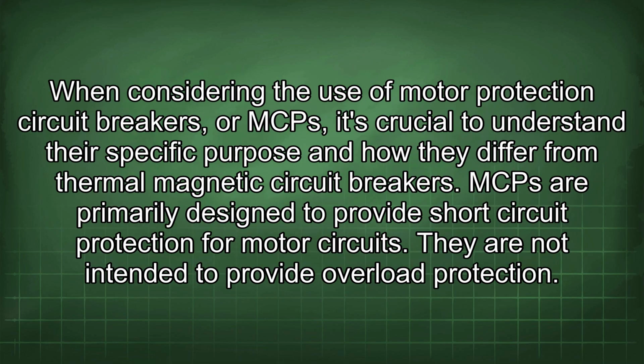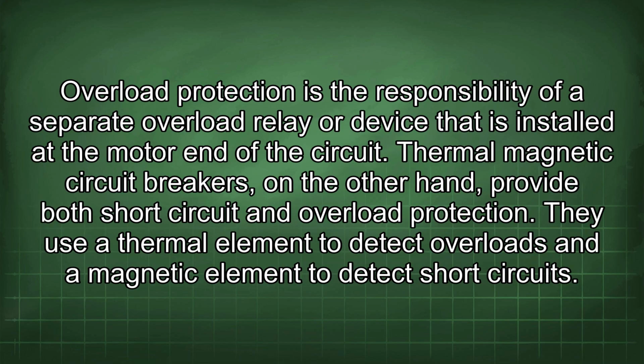When considering the use of motor protection circuit breakers, or MCPs, it's crucial to understand their specific purpose and how they differ from thermomagnetic circuit breakers. MCP are primarily designed to provide short-circuit protection for motor circuits. They are not intended to provide overload protection. Overload protection is the responsibility of a separate overload relay or device that is installed at the motor end of the circuit.